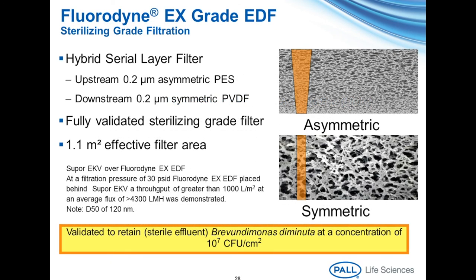As Martha will discuss Fluorodyne EX-EDF in her presentation, I should explain what it is. Fluorodyne EX-EDF is a hybrid serial layer filter that utilizes an upstream asymmetric polyethersulfone membrane over a downstream symmetric PVDF layer. The upstream PES layer is asymmetric with a narrowing pore structure as fluids pass through. The downstream PVDF layer is symmetric with a consistent 0.2 micron rated pore structure throughout. Fluorodyne EX-EDF is a fully validated sterilizing grade filter and should be employed as the final filter for high-risk emulsion solutions.